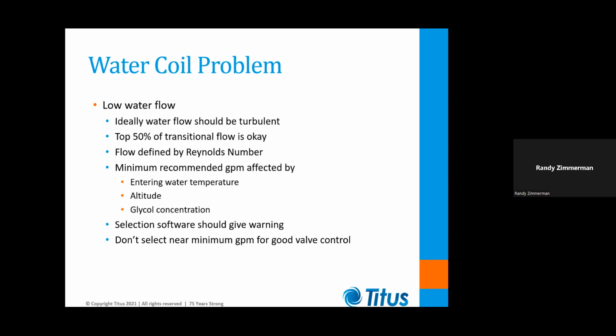So hopefully you're dealing with selection software that gives you a warning, because if you drop below the minimum recommended GPM, a program is going to probably overpredict the capacity. It's not going to be the correct capacity. It's going to overpredict. So you don't want to go anywhere near the minimum GPM because if you select at the minimum GPM, you're probably going to have poor valve authority on your control valve.